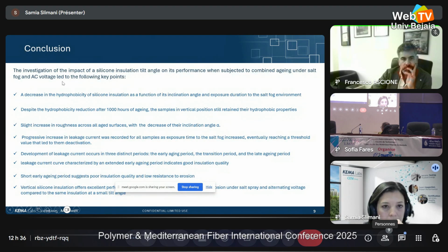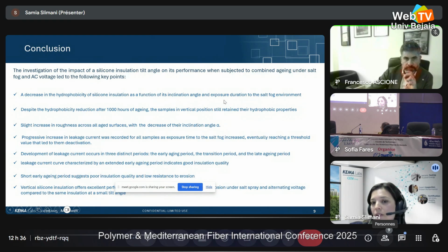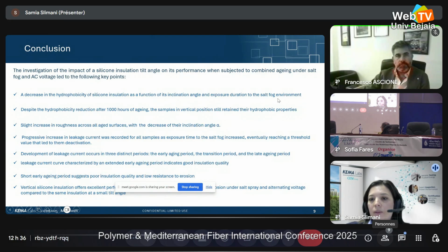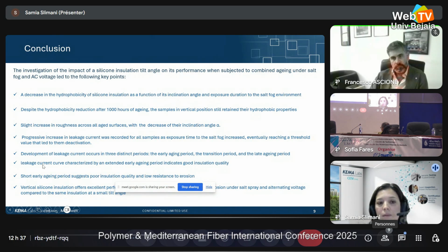As a conclusion, the following key points are found. A decrease in the hydrophobicity of silicone insulation as a function of its inclination angle and exposure duration to the salt fog environment. Despite the hydrophobicity reduction after 1000 hours of aging, the samples in vertical position still retained their hydrophobic properties. Slight increase in roughness across all aged surfaces with the decrease of their inclination angle. Progressive increase in leakage current was recorded for all samples as exposure time to the salt fog increased, eventually reaching the critical value that led to their deactivation.